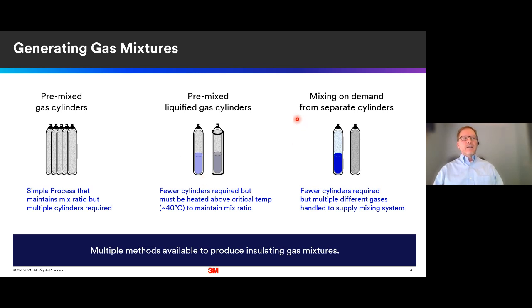And then finally, you could mix the materials on demand. So basically, you'd have to handle individual cylinders of each component. So as Renee described, that could be 2 or 3 components in a mixture. So it has that complication of individual compounds being managed and handled, and you'd have to have the equipment that would do the proper mixing ratio. And in reality, all 3 of these types of methods are already being used and have been used for the type of equipment that Renee described that's already operating on the grid.